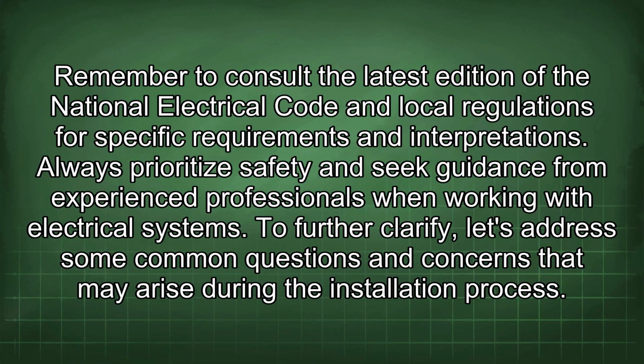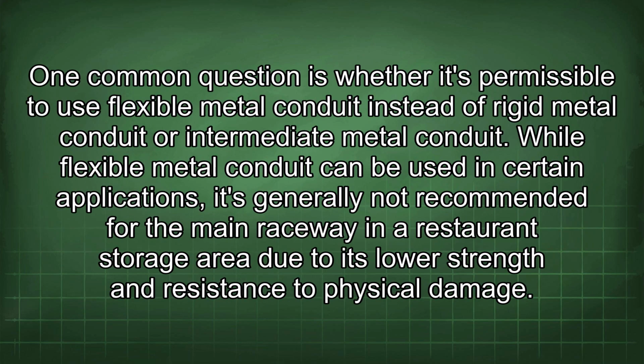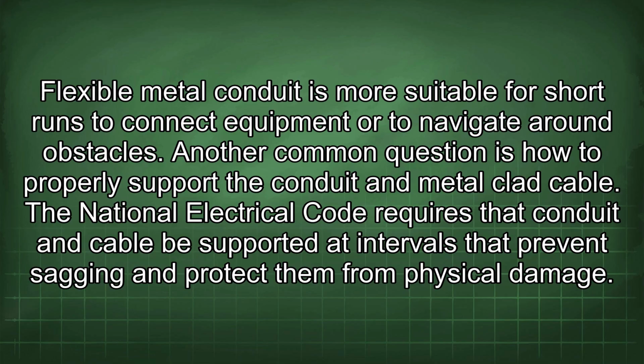To further clarify, let's address some common questions and concerns that may arise during the installation process. One common question is whether it's permissible to use flexible metal conduit instead of rigid metal conduit or intermediate metal conduit. While flexible metal conduit can be used in certain applications, it's generally not recommended for the main raceway in a restaurant storage area due to its lower strength and resistance to physical damage. Flexible metal conduit is more suitable for short runs to connect equipment or to navigate around obstacles.